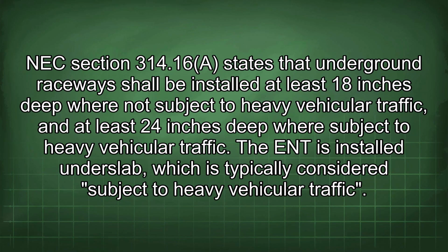NEC Section 314.16 states that underground raceways shall be installed at least 18 inches deep where not subject to heavy vehicular traffic and at least 24 inches deep where subject to heavy vehicular traffic. The ENT is installed under slab, which is typically considered subject to heavy vehicular traffic.